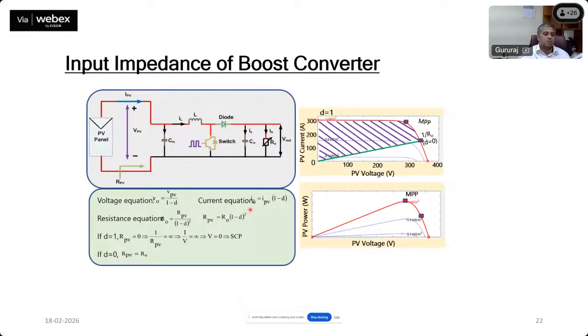The current equation is just the opposite: I0 equals IPV times 1 minus D. This is like a conventional step-up transformer. If the voltage boosts up, the current bucks, so output current will be less than input current. Hence the power remains almost the same from input to output, except for losses in the inductors and switches. So more or less, it is highly efficient.